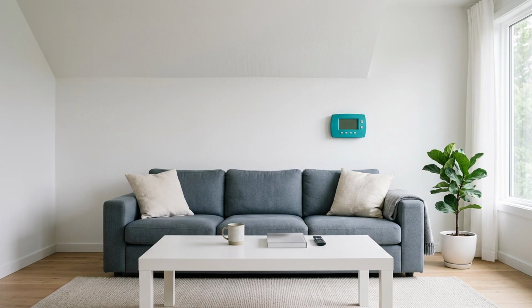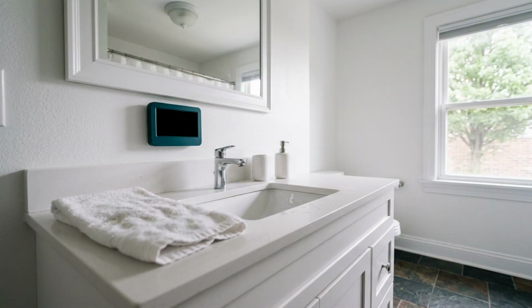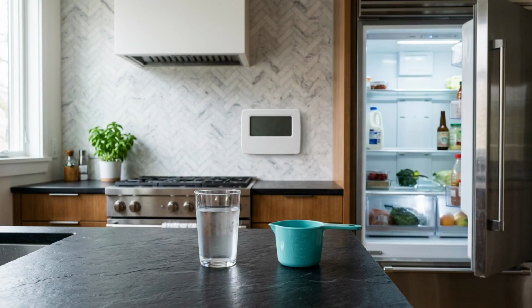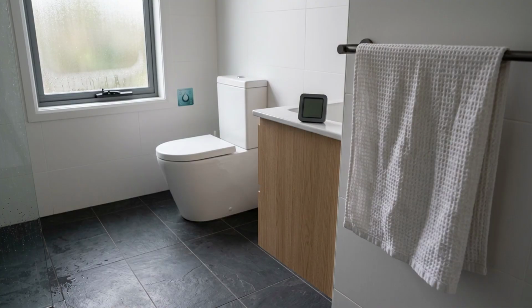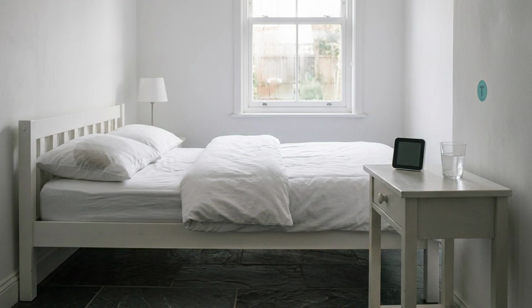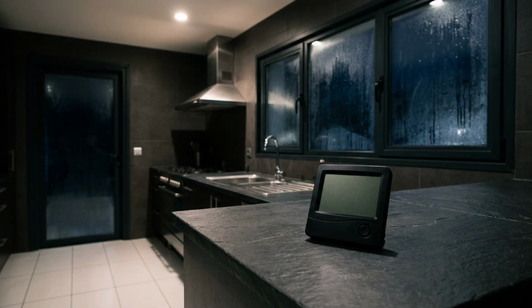The Environmental Protection Agency advises keeping indoor relative humidity below 60% if possible, and ideally between 30 and 50%. The Centers for Disease Control and Prevention gives a more conservative mold prevention target, no higher than 50% all day. Those numbers are guidance targets. They are not an on-off switch where 49 proves a home is dry and 60 creates mold instantly. A room reading has to be interpreted with the conditions around it.